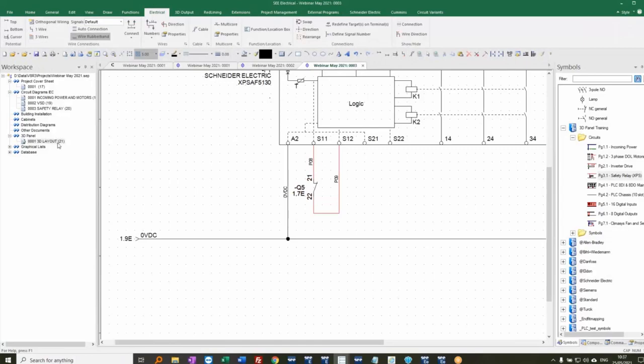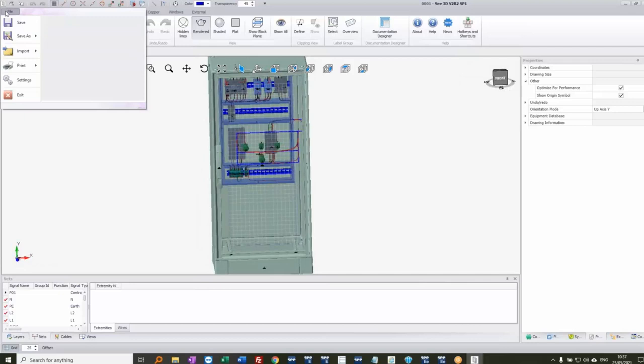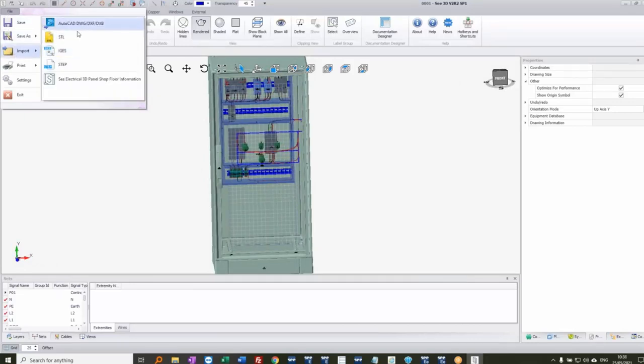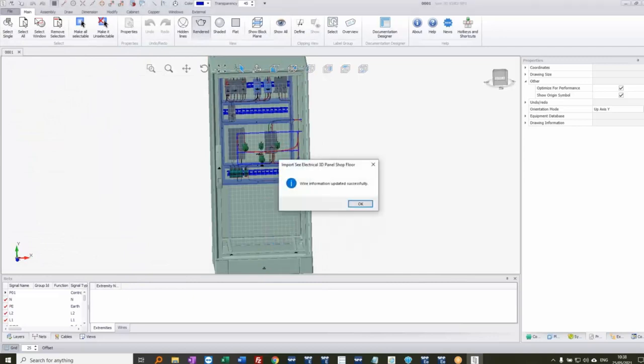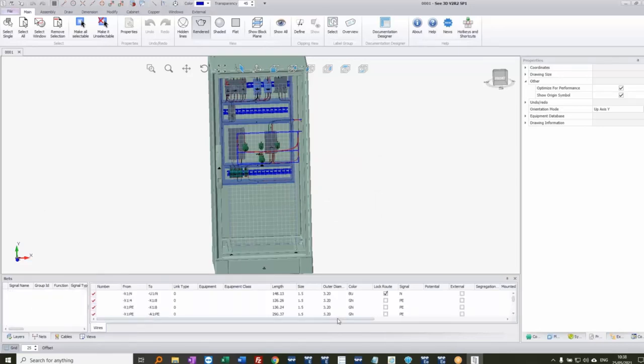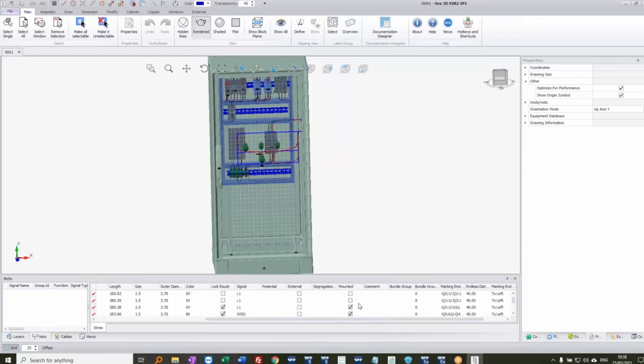This information is saved as you work — you can close the Shop Floor module, come back later, and finish off. Back in SEE Electrical, if I open the 3D layout, I can import the shop floor data back in. Under File > Import, alongside standard graphics like AutoCAD, STL, IGES, and STEP, there's a '3D Shop Floor' option. Importing it updates the wiring information — scrolling to the right in the wire list, I can see which wires have been marked as mounted and verified.